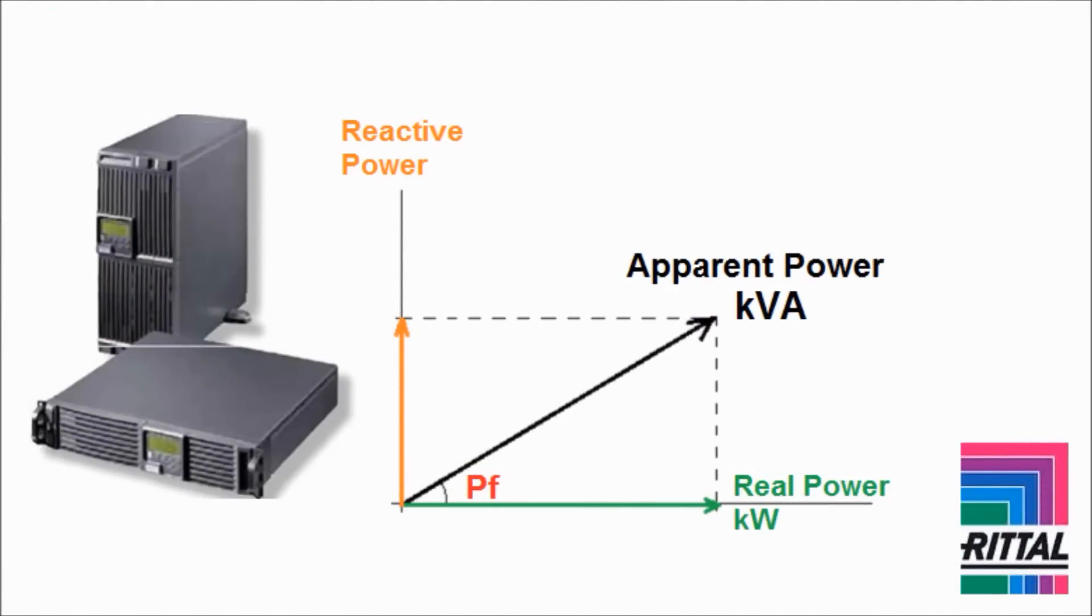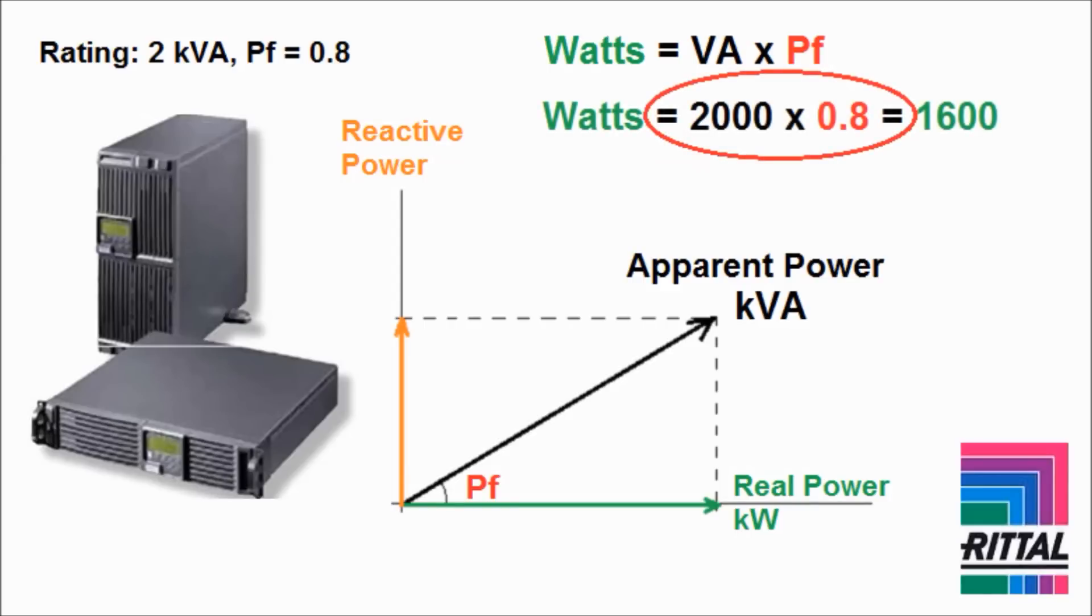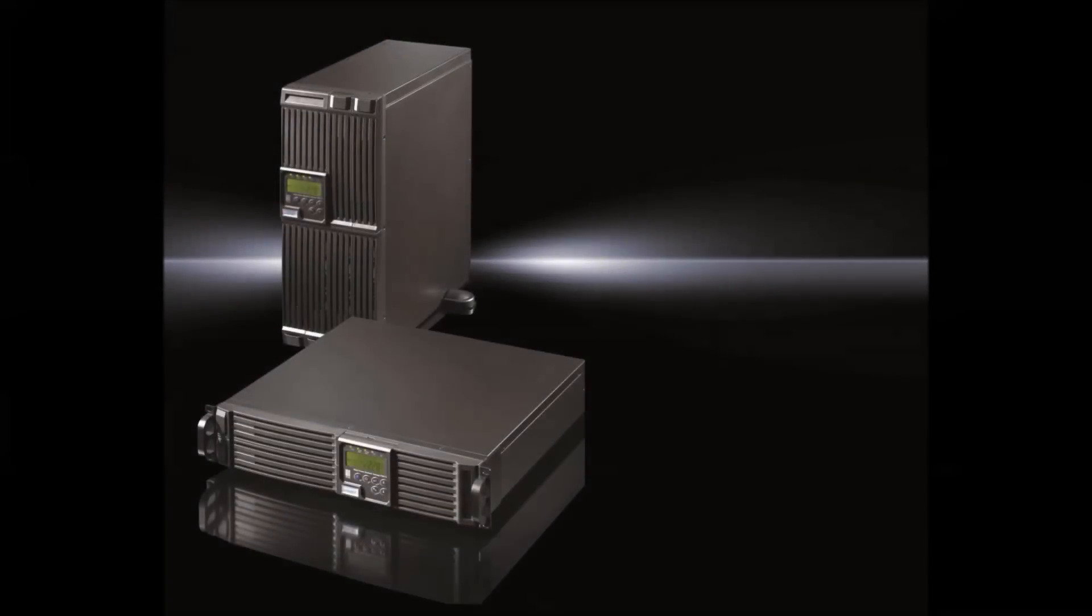Similarly, for a 2 kVA UPS with a power factor of 0.8, the formula reveals that it supports up to 1.6 kW, since 2000 multiplied by 0.8 equals 1600.